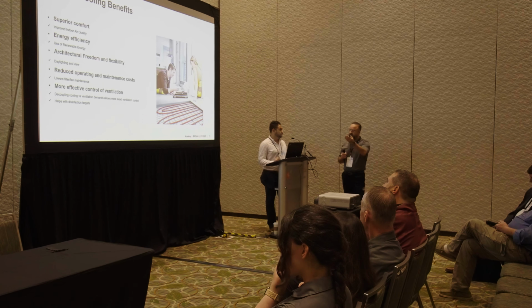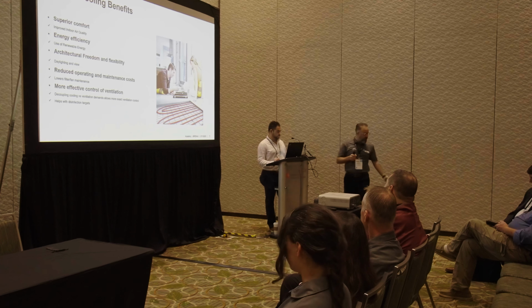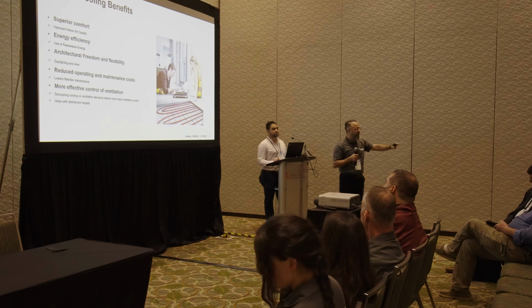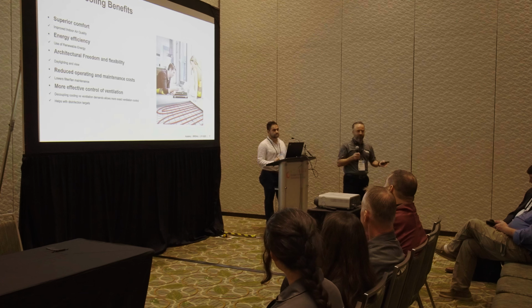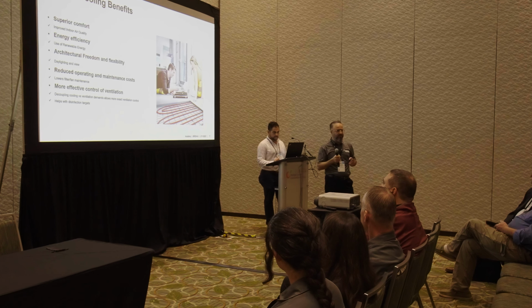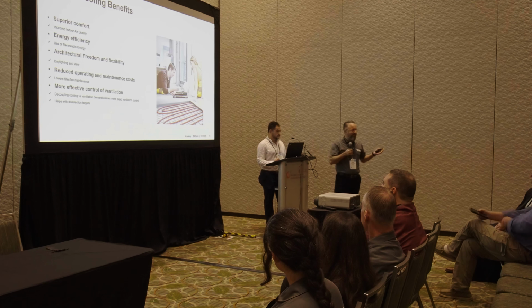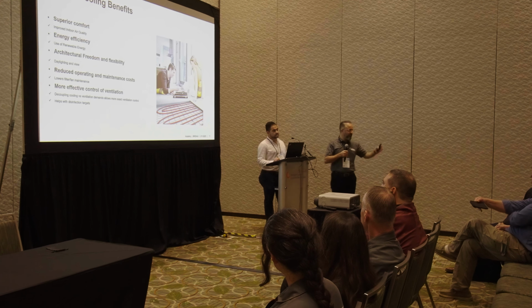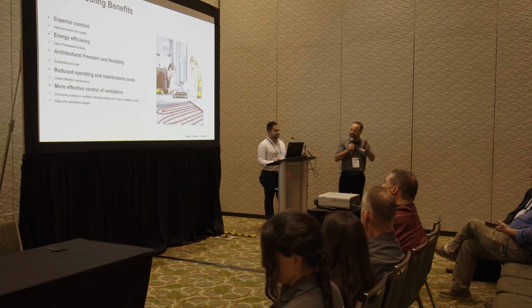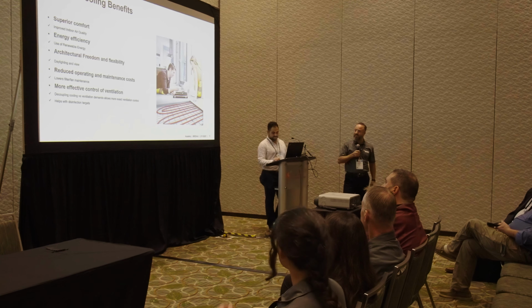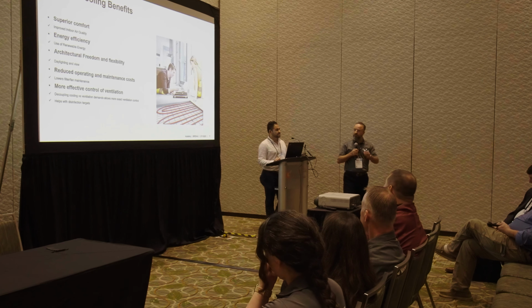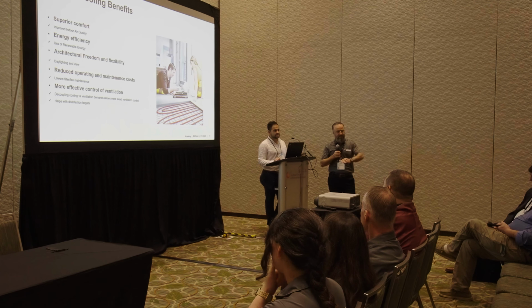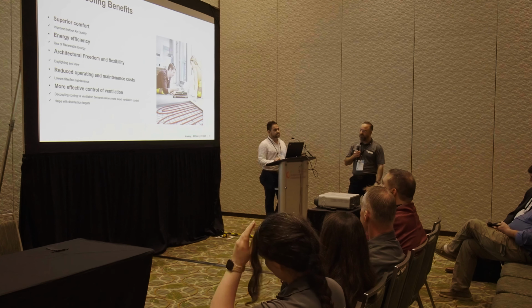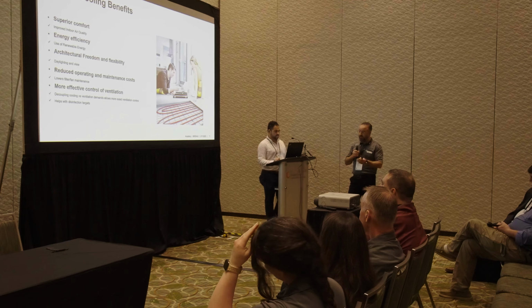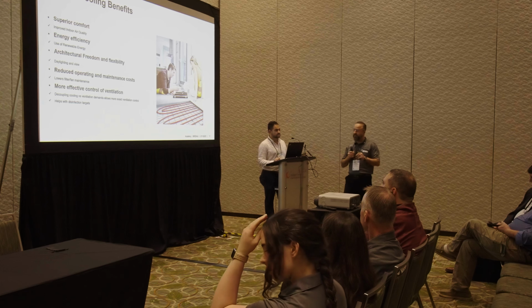And also the maintenance cost. With the system, you run tubing in your floor and you pour the concrete. No one sees the system. There is no exposed part of the system that requires any crazy maintenance. The only part you may check once a year is the manifold. You want to make sure no one took a piece and ran away. Everything is still there. That's the only maintenance you want to do on this. So when you are working with this, you are lowering your cost of the filters and the fan maintenance and every other moving part.